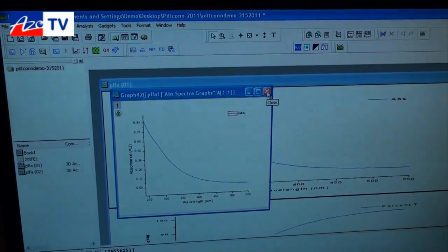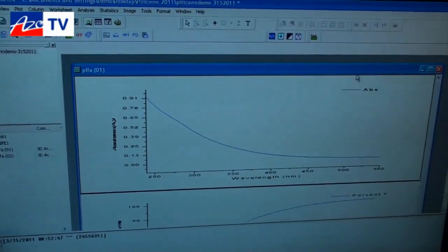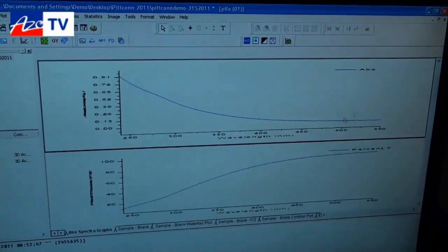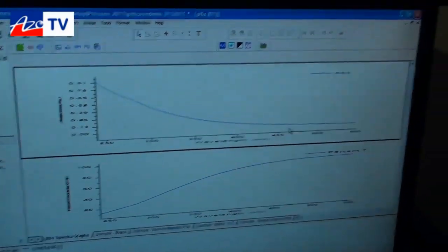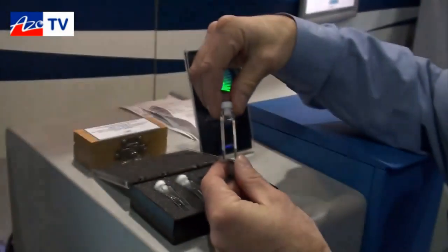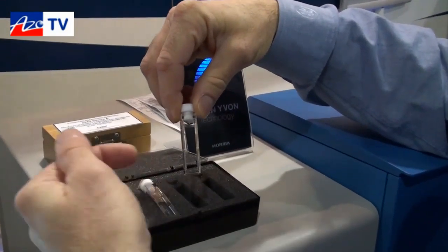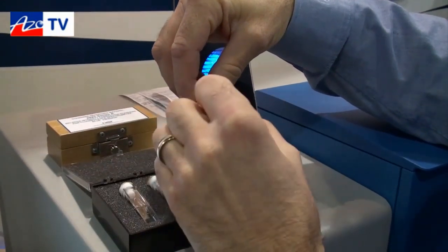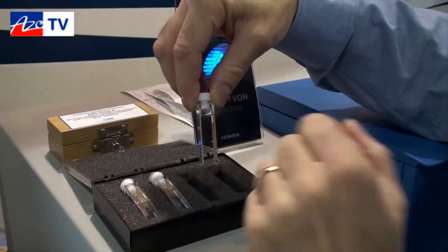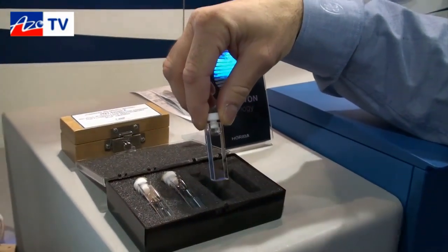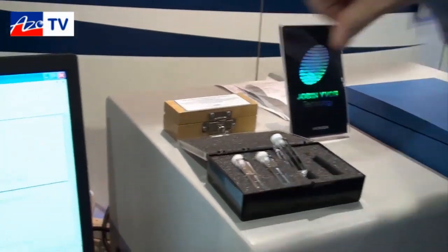The other reason the absorption is important is because the fluorescence sample holder cuvette, the sample that's inside of our cuvette, can actually when the exciting light passes through and the fluorescence is emitted, part of the fluorescence light can be reabsorbed and that can distort the spectrum.